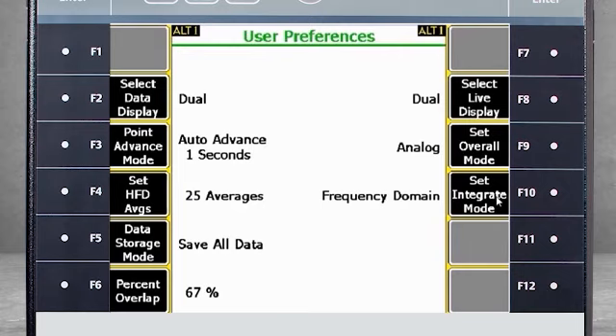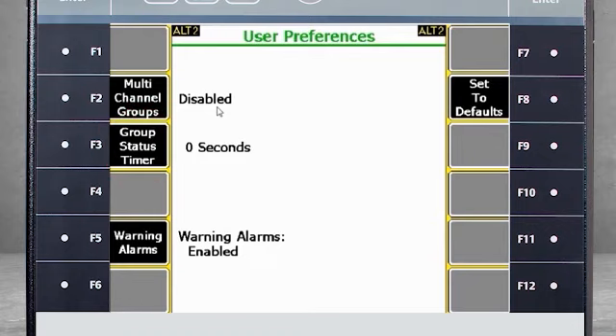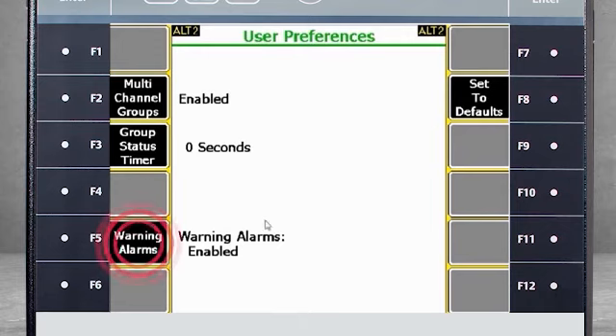Under User Preferences, there are more function keys available on the Alt-2 page. F2 multi-channel groups are enabled, meaning you will allow for simultaneous data collection on up to four channels of data. When disabled, the data will not be collected simultaneously. F3 Group Status Timer is set to zero seconds, meaning you will not see a summary screen after a group point measurement. If you set that to five seconds, you would see a summary screen of the group points for five seconds after collection. F5 allows you to enable or disable warning alarms.